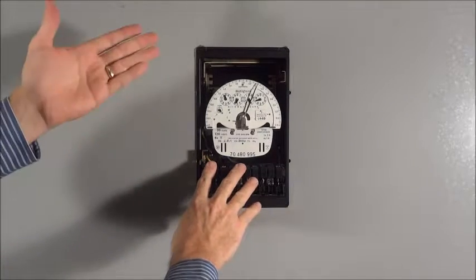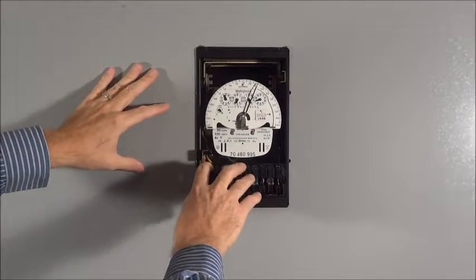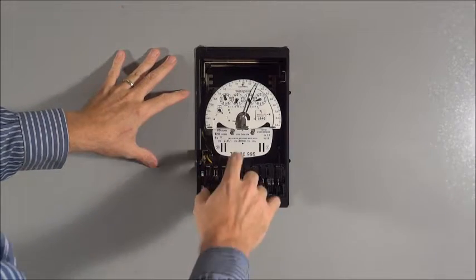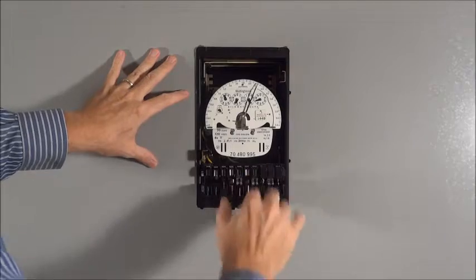Then you can do this with the power on or you can shut the power off as well. But if you open up the knife switches this will short the CTs.